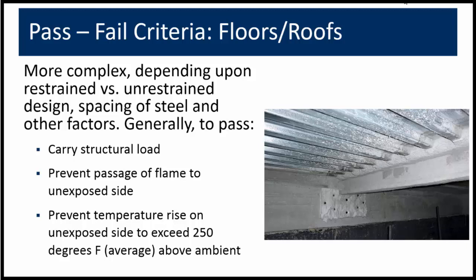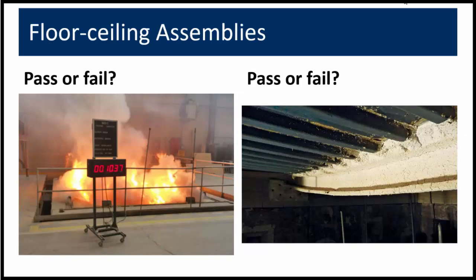Pass-fail criteria for floor and roof assemblies: it affects whether or not the assembly is designed to be a restrained or unrestrained design, as well as the spacing of steel. Some familiar criteria include the ability to carry the load for the prescribed time, preventing the passage of flame and hot gases to the opposite side of the assembly, and limiting temperature transmission to not more than 250 degrees average above ambient. The photo on the left shows flame passage through the assembly — that is a fail. The photo on the right shows the same beam with some deflection after fire exposure, but it did not collapse and is considered acceptable.